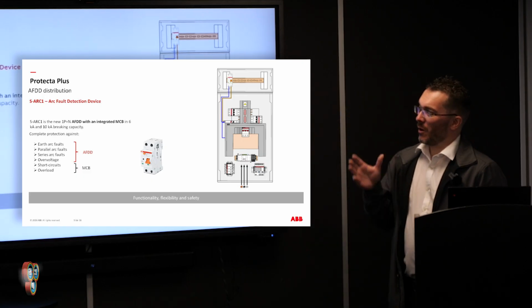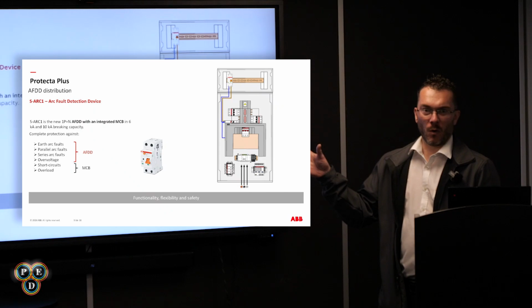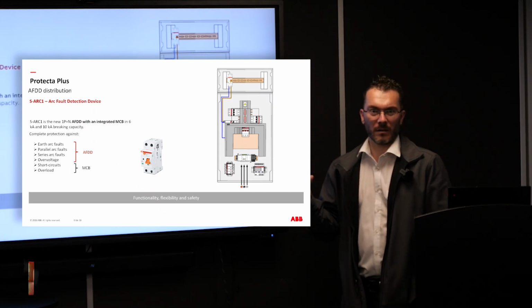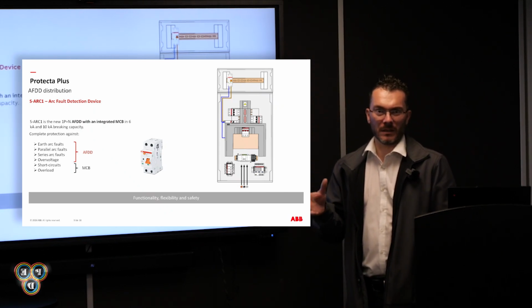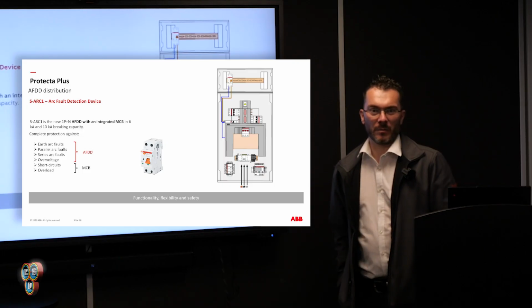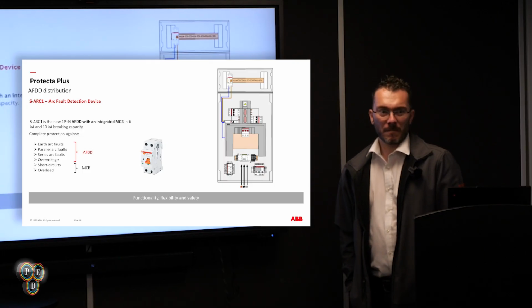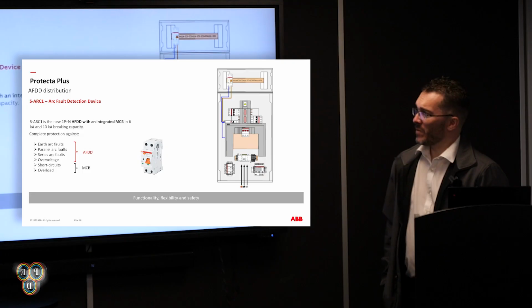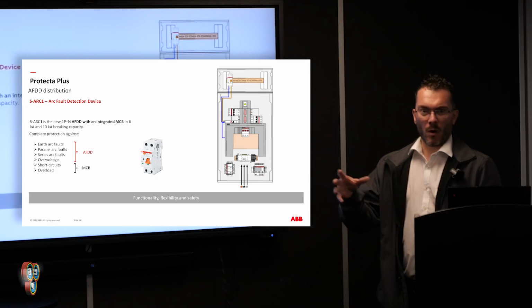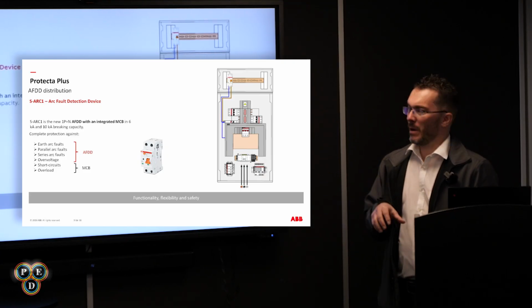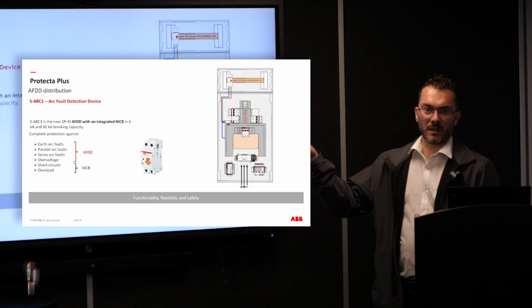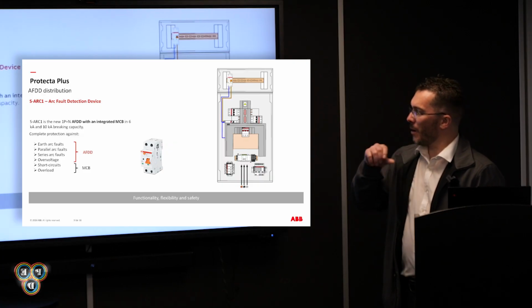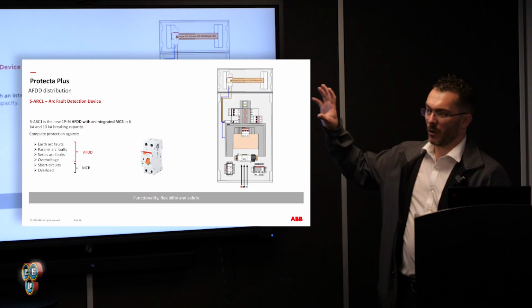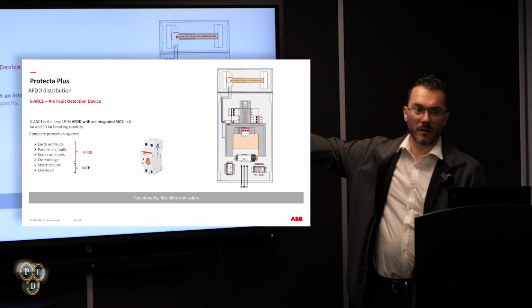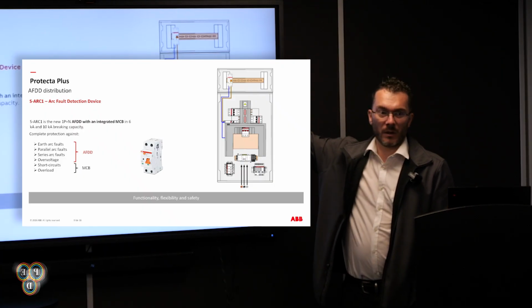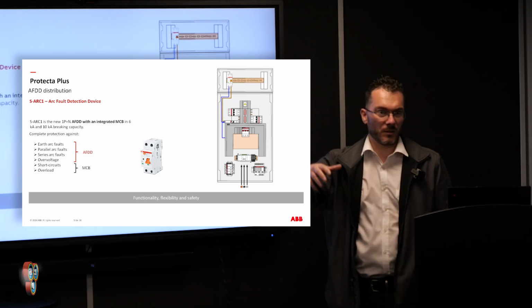Yeah. So these are going to become more and more common. I can eventually see the demise of the MCBs, and everything will be RCBO or AFDD. I think everything's going to go AFDD. Yeah, by the look of it. Which is why we're putting quite a bit of research and development into reducing the amount of space and reducing it down to a single module device. However, currently our solution on a 3-phase install would be to fit an RCBO in the distribution board and then feed that to an AFDD either in the top or side extension box.